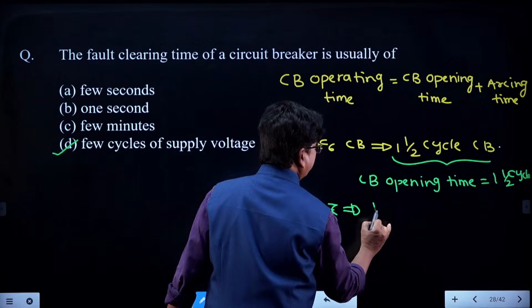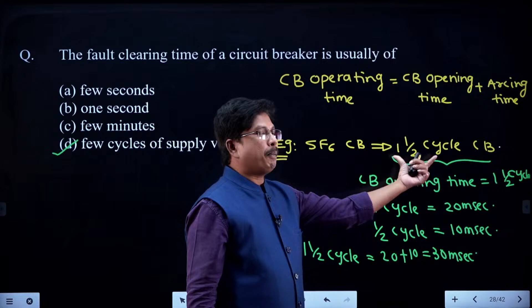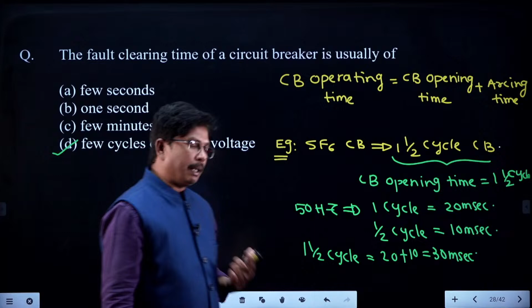For example, an SF6 circuit breaker is a 1.5 cycle circuit breaker. Whenever we say 1.5 cycle circuit breaker, it has a CB opening time of 1.5 cycles. Students, for a 50 Hz system, the time for one cycle is 20 milliseconds. The time for half cycle is 10 milliseconds. Whenever you say 1.5 cycle, the time will be 20 plus 10, that is 30 milliseconds. Means the CB opening time will be 30 milliseconds for a 1.5 cycle circuit breaker. Generally we mention 1.5 cycle circuit breaker like that.